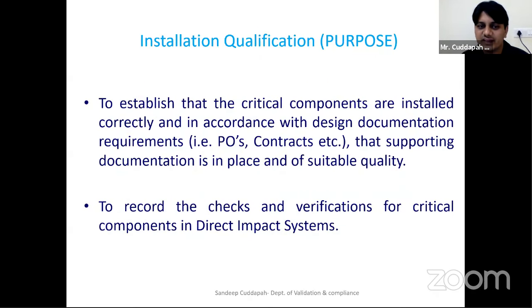Then what is the purpose of installation qualification? Actually, it is to establish that the critical components are installed correctly and in accordance with the design documentation and requirements. So based on purchase orders or contracts, the supporting documentation is in place and of suitable quality. In installation qualification, we verify against your purchase request. You have given a purchase request to a vendor, and the vendor supplied. Whether he supplied correctly as per your purchase list or not, you will verify in the installation qualification.